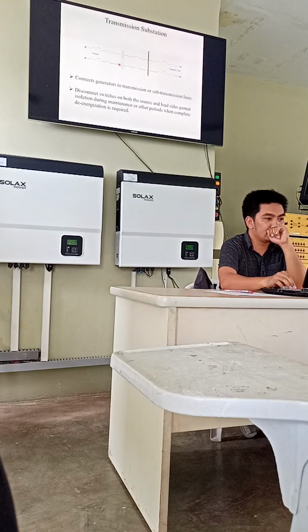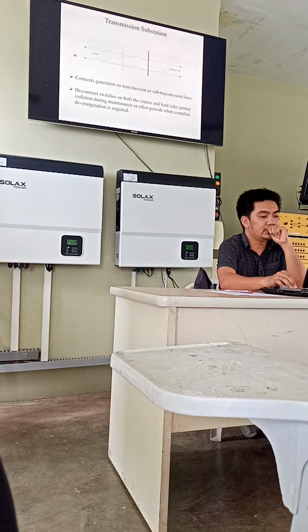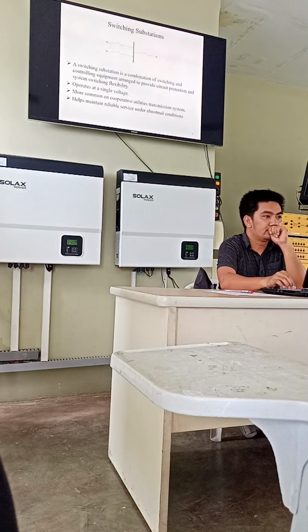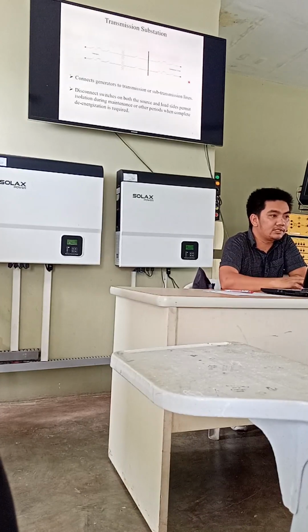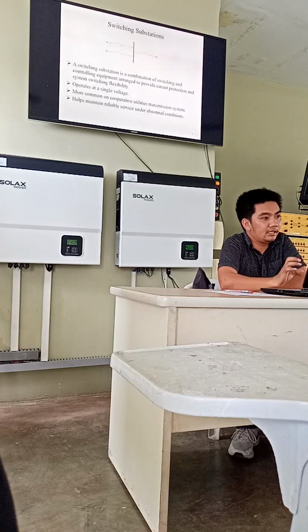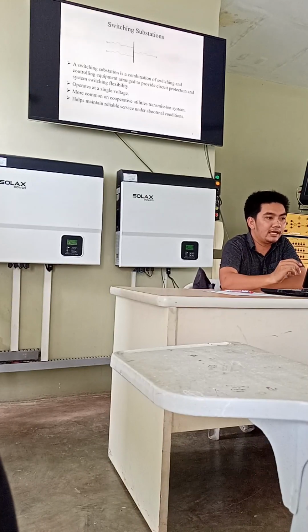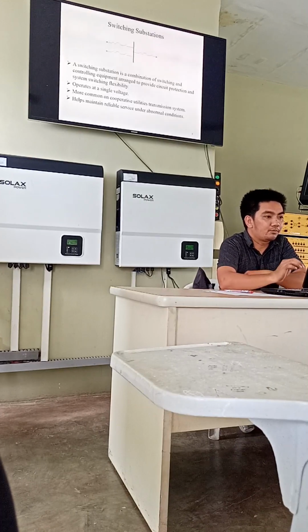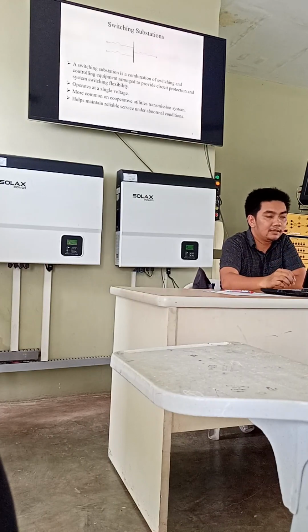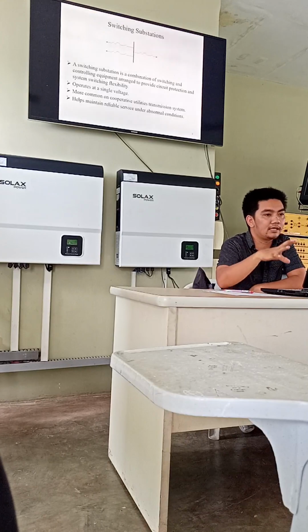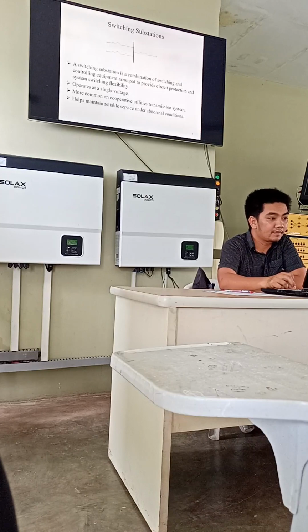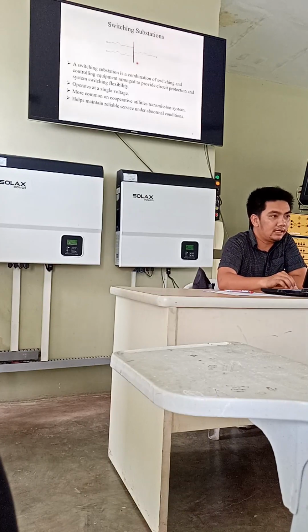And it disconnects the switch on both the source and the load side, permitting isolation during maintenance. Whereas the switching substation, you can see that the transmission substation has a transformer, no? The switching substation could have no transmission transformer at all. Basically, what it provides is flexibility and interconnection in the system, no? It's a combination of switching and controlled equipment to provide circuit protection and switching flexibility, transfer of loads or reconfiguration in the transmission system. Basically it operates at a single voltage since there's no transformer found in these substations.